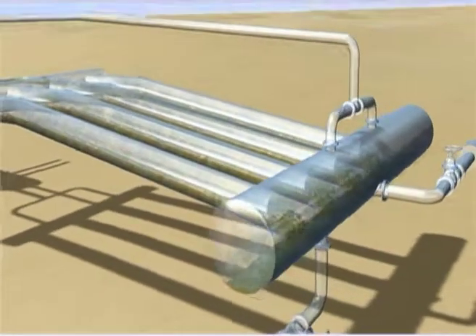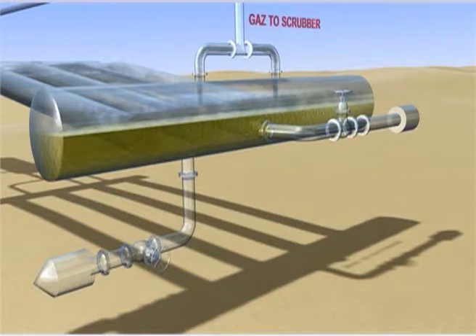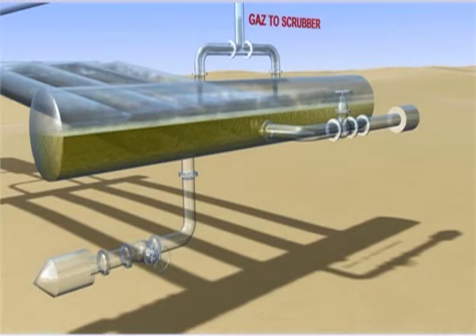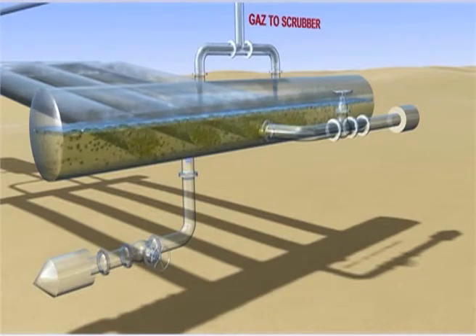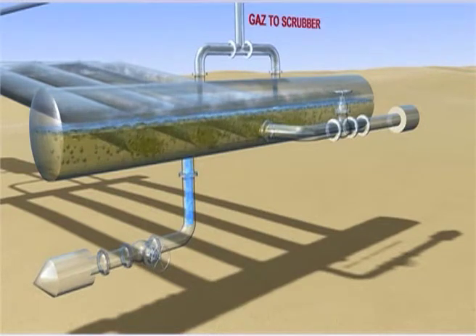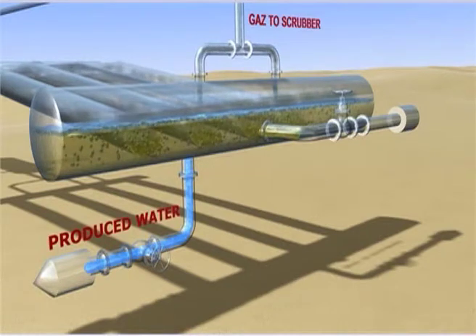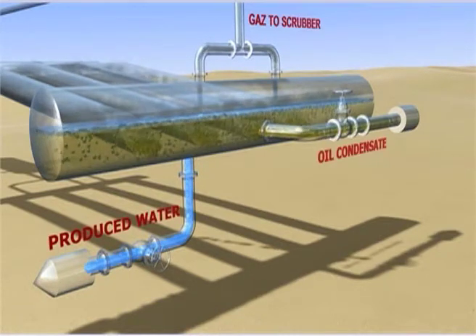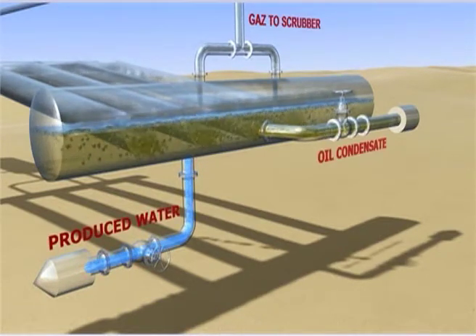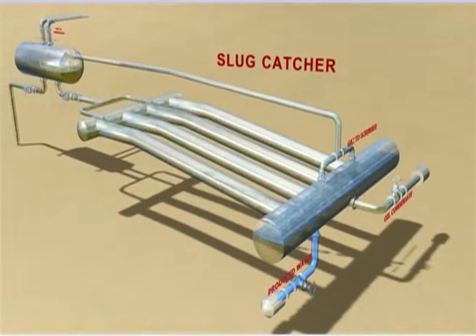The distribution manifold takes the incoming gas-liquid stream, slows it down, and splits it into several smaller streams to allow uniform flow and activates the gas-liquid separation. The length, size, and number of these chambers are a combined function of gas flow, gas chemistry, and other known conditions.